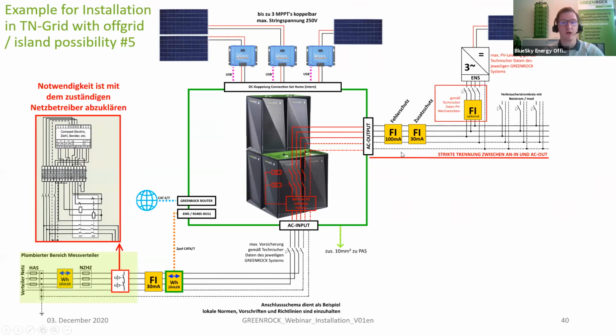But please always be aware of the maximum values inside the datasheet. For example, the transfer current from AC in to AC out per phase on a GreenRock home system is 32 amps, so please be aware of that 32 amp transfer current — that's the exact name used in the technical datasheet.